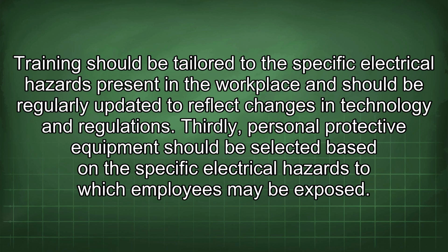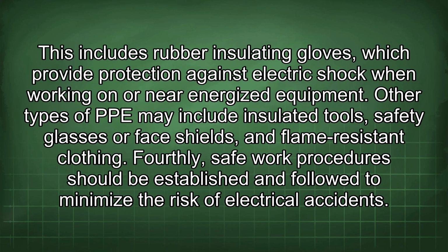Thirdly, personal protective equipment should be selected based on the specific electrical hazards to which employees may be exposed. This includes rubber insulating gloves, which provide protection against electric shock when working on or near energized equipment. Other types of PPE may include insulated tools, safety glasses or face shields, and flame-resistant clothing.